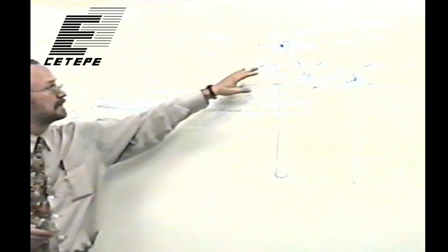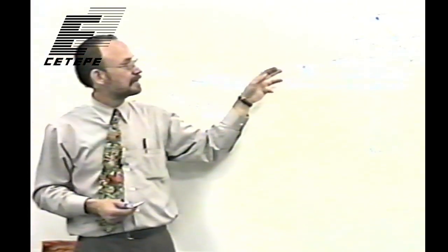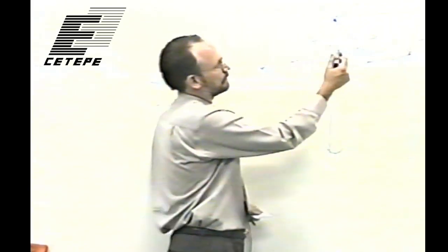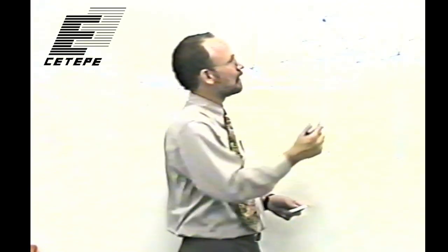So there's all kinds of things that they do at Kodak and DuPont to try to help this. The most common thing you do is you add a black opaque powder to the binder around the phosphor. So the black powder will absorb light and keep it from going a great distance in the screen. Another thing that they almost always do is they put a reflective layer.